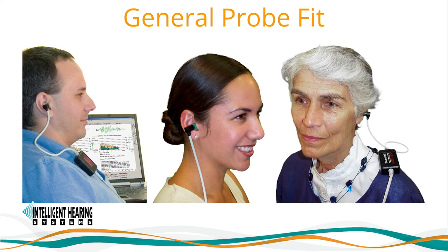Do not hold the probe while you are administering an OAE test. By holding the probe in the patient's ear, you may unintentionally push it against the wall of the ear canal, preventing a signal from getting through, and may also unintentionally create noise. If the probe is properly placed, it should stay in place by itself. Clip the probe speaker box to the patient or side of the patient. If testing a baby, you can clip the probe to the baby's blanket or bassinet. This takes the weight off the probe microphone and keeps it from pulling out of a baby's ear.